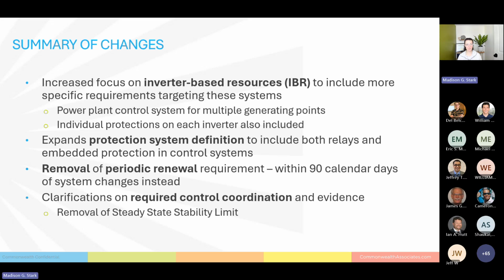It also expands the protection system definition to include both relays, so standalone relays outside of the generator, as well as the embedded protection in the control system. So within the exciter, there's some embedded protection. Within the inverters themselves, there's some embedded protection. So it kind of clarifies what protection system actually means and which things are included in the protection system versus other components of the system.